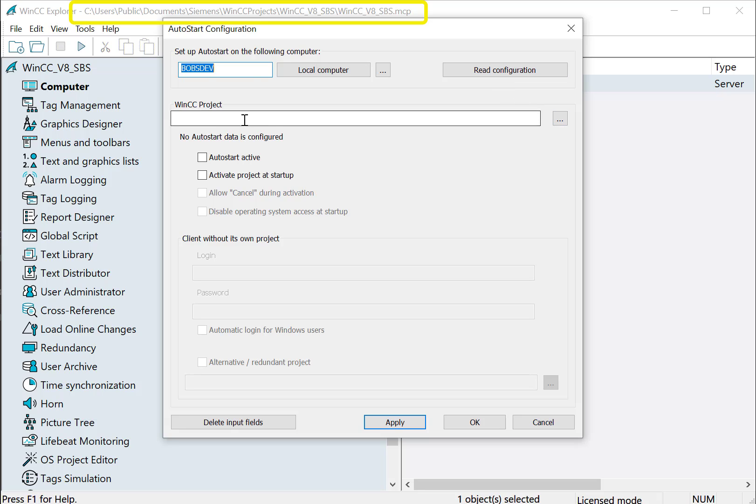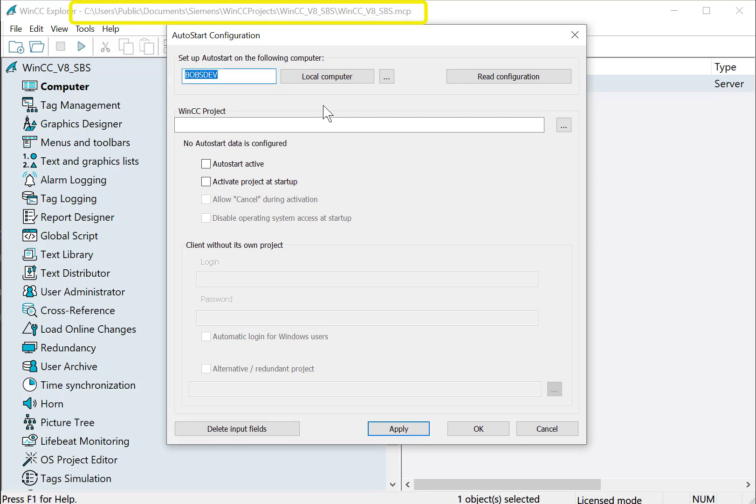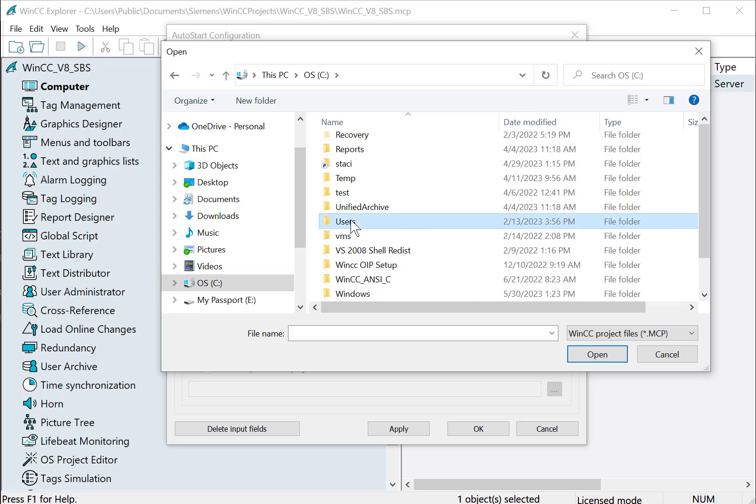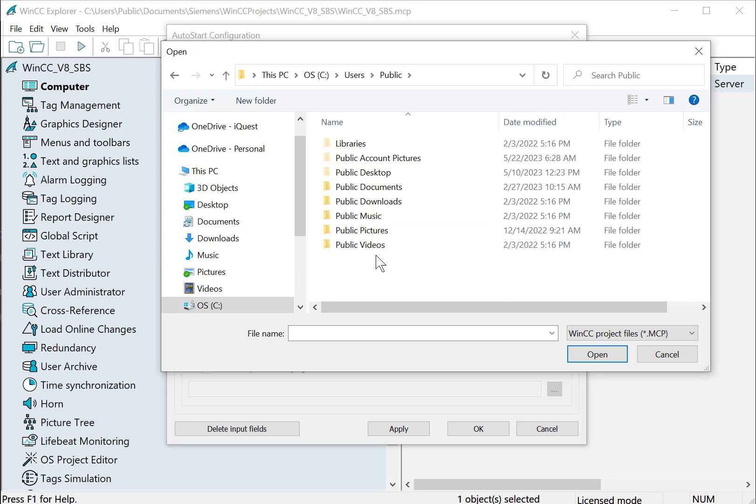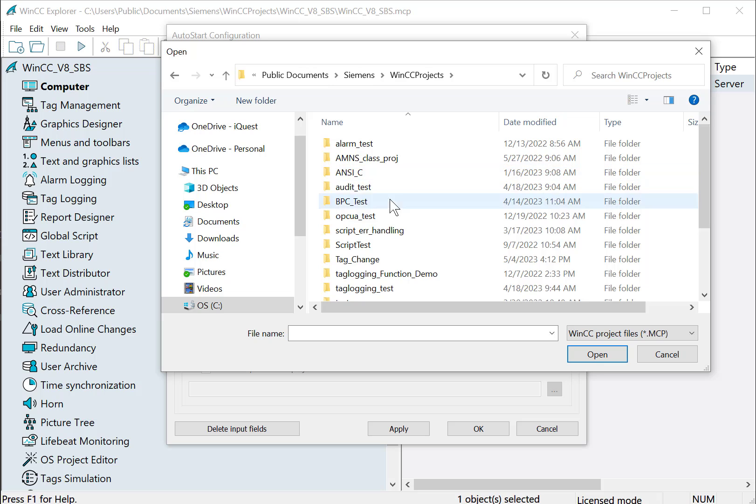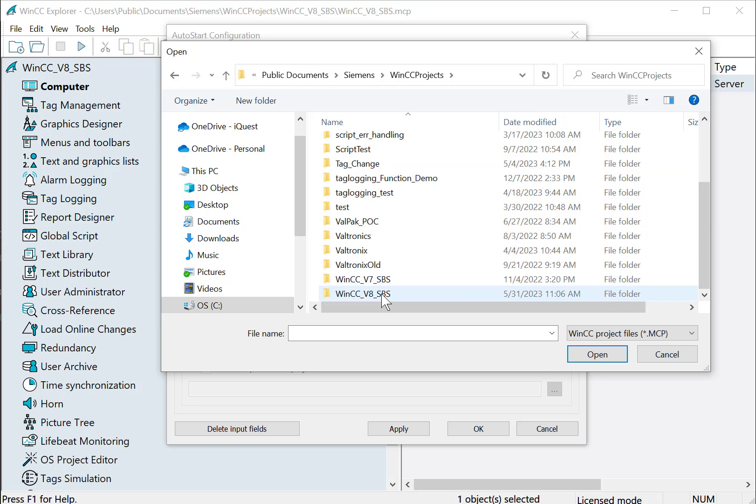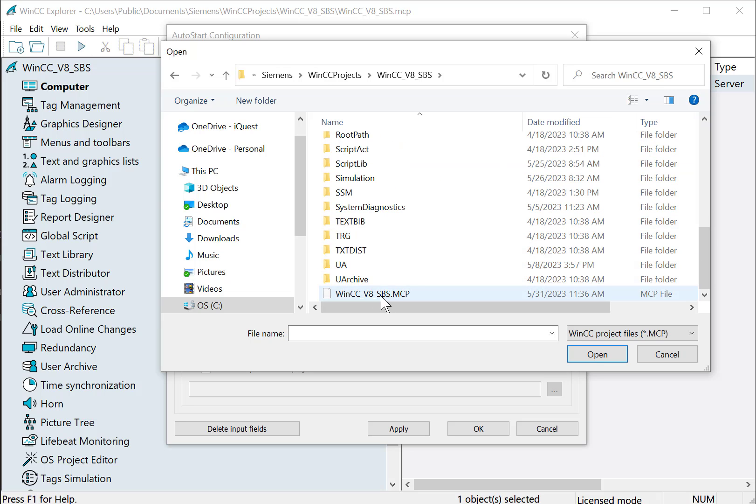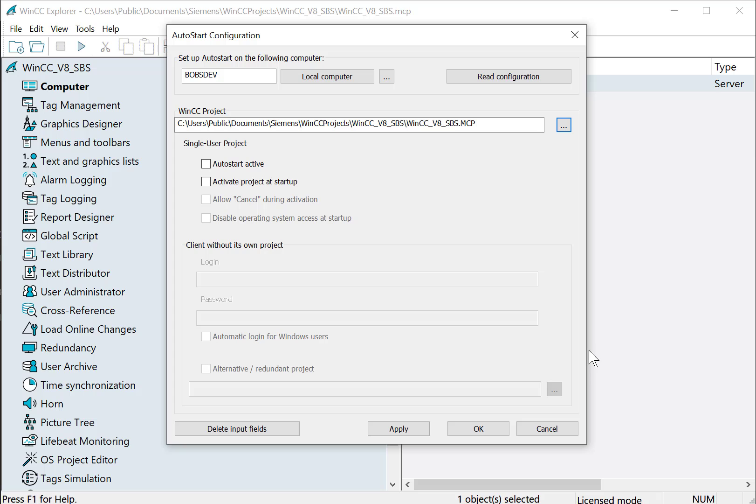We just have to find our WinCC project and you can see the path here in the Control Center title bar. And we'll choose the project's MCP file. And if we activate Auto Start, this will automatically open the project. And if we check Activate, it'll automatically send it to runtime.